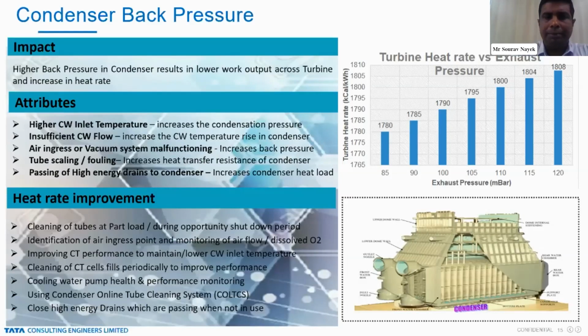Higher CW inlet temperature: if the cooling tower performance is deteriorated and cooling water inlet temperature is increased, this will increase the condenser back pressure and ultimately the turbine work will get reduced. Insufficient CW flow, because of the malfunctioning of the CW pump or the improper condition of the CW pump, will also increase the temperature rise in the condenser.